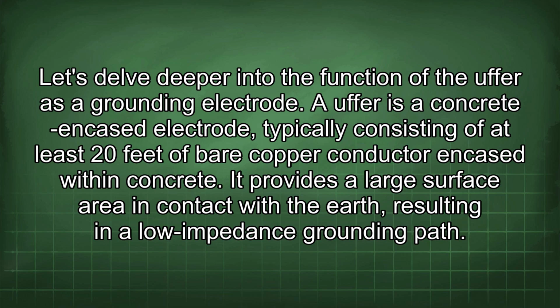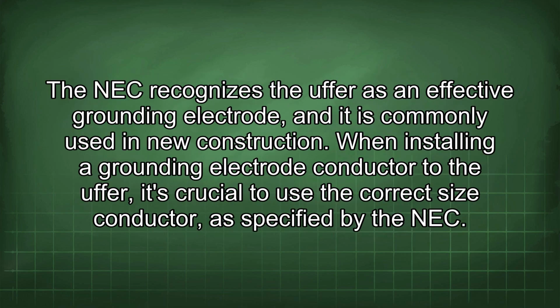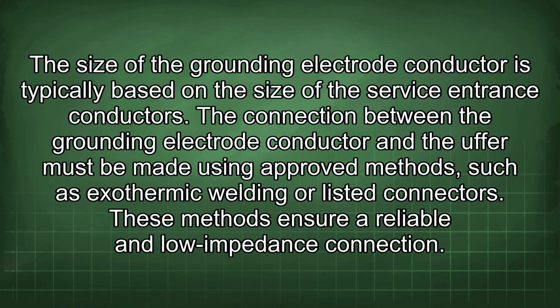A Ufer is a concrete encased electrode, typically consisting of at least 20 feet of bare copper conductor encased within concrete. It provides a large surface area in contact with the earth, resulting in a low impedance grounding path. The NEC recognizes the Ufer as an effective grounding electrode, and it is commonly used in new construction. When installing a grounding electrode conductor to the Ufer, it's crucial to use the correct size conductor, as specified by the NEC. The size of the grounding electrode conductor is typically based on the size of the service entrance conductors. The connection between the grounding electrode conductor and the Ufer must be made using approved methods such as exothermic welding or listed connectors. These methods ensure a reliable and low impedance connection.